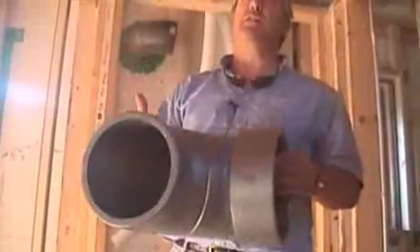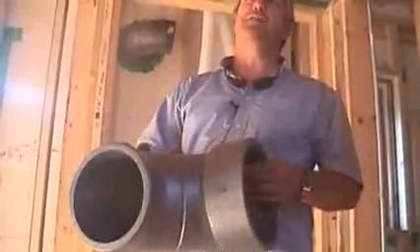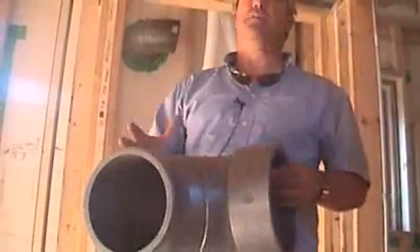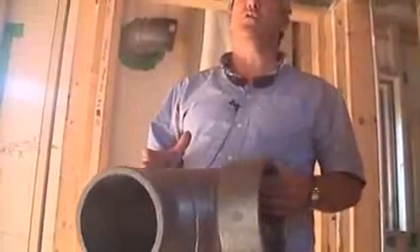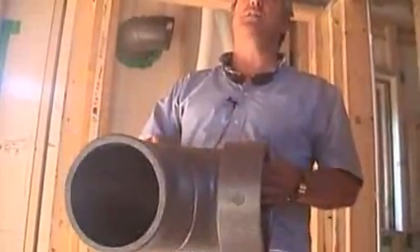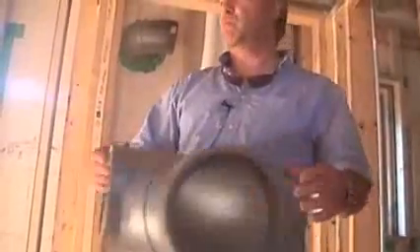This is R5, and you can add insulation to that. You can wrap it and so forth. But unlike a metal duct that you would then insulate, the problem with that is oftentimes you get condensation between the metal and the insulation, and that causes corrosion. This won't have any condensation, and then you can add insulation to it for just pure thermal.